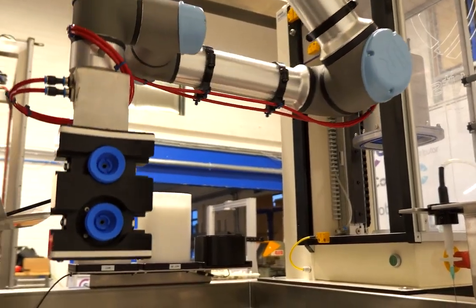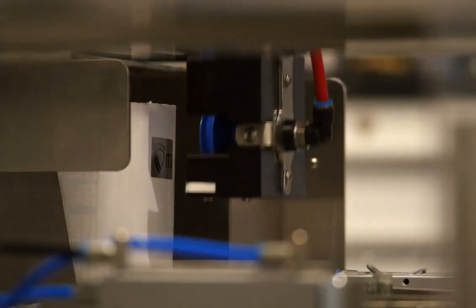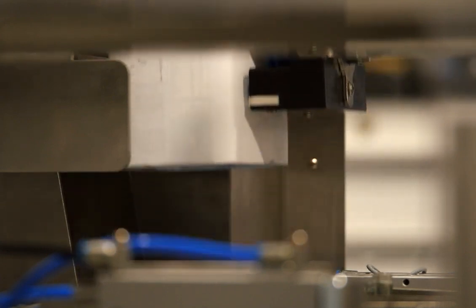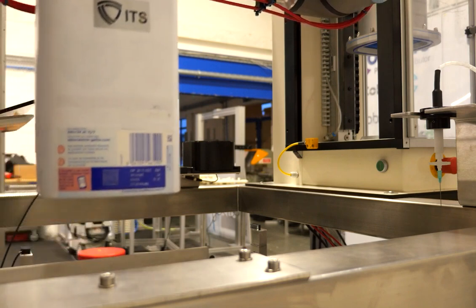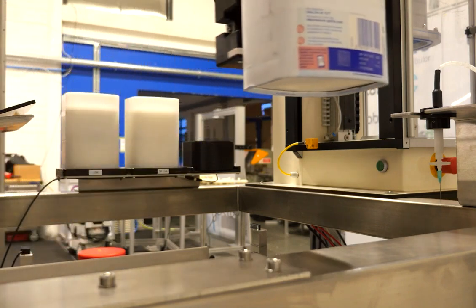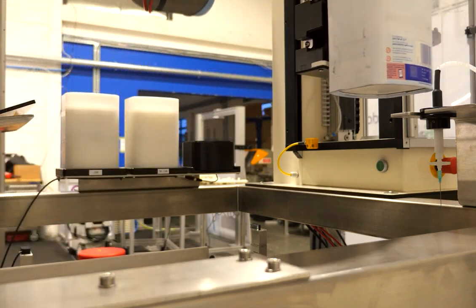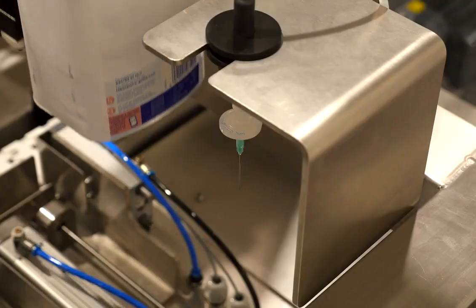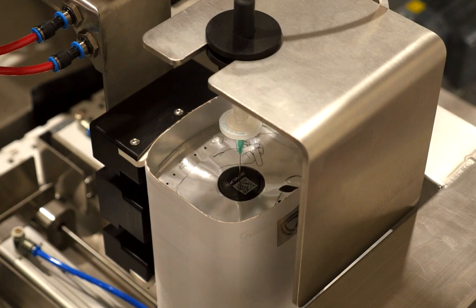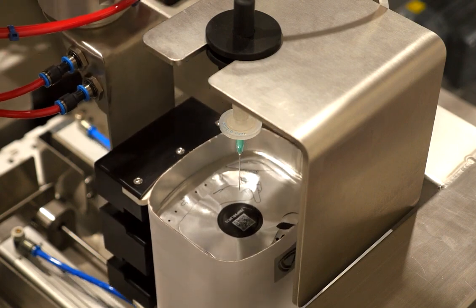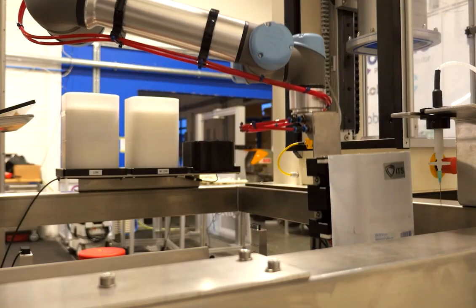This was important to the end client because they didn't want to have lots of different types of tooling. Here you can see the seal being tested, and the cell records the entire force and all the codes, consolidates them together into a database. This also takes out the need for somebody to input this data, where it could be put in wrong and the codes might not align.